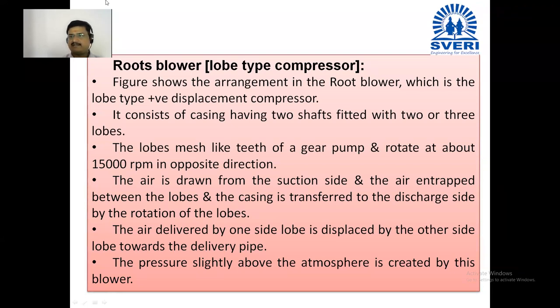Prajakta, you can go ahead. Roots blower or lobe type compressor. Figure shows the arrangement in the roots blower, which is the lobe type positive displacement compressor. It consists of a casing having two shafts fitted with two or three lobes.